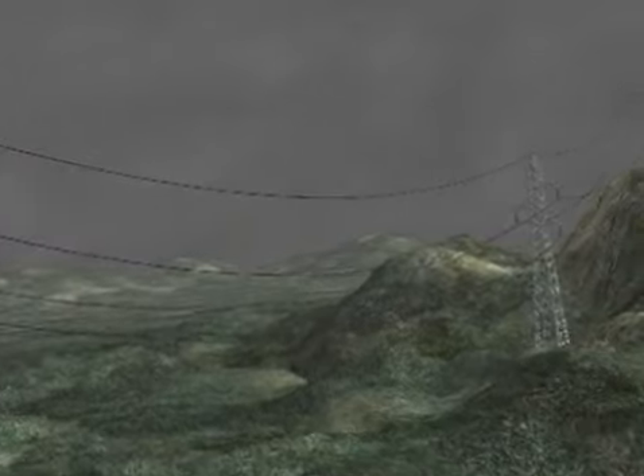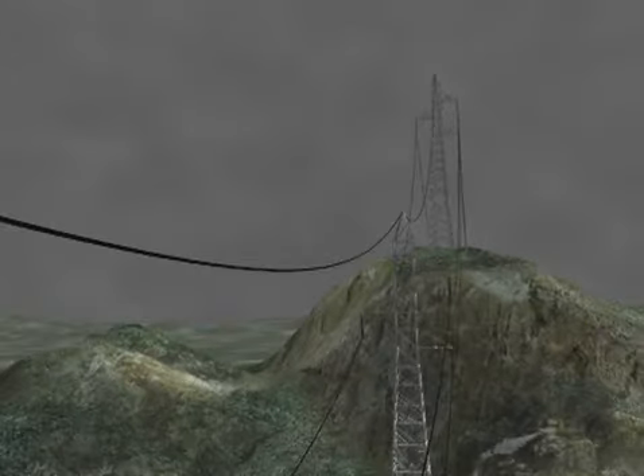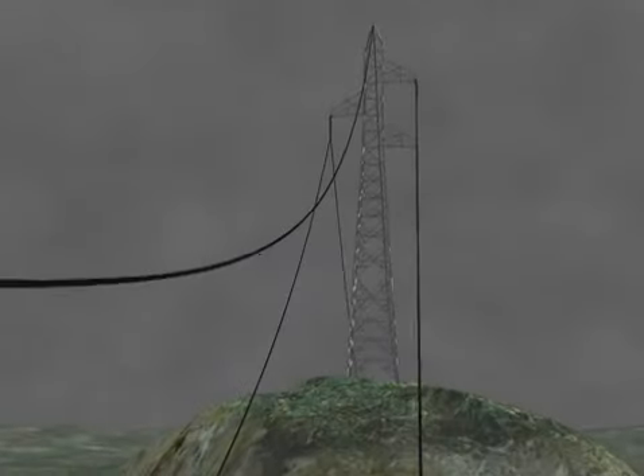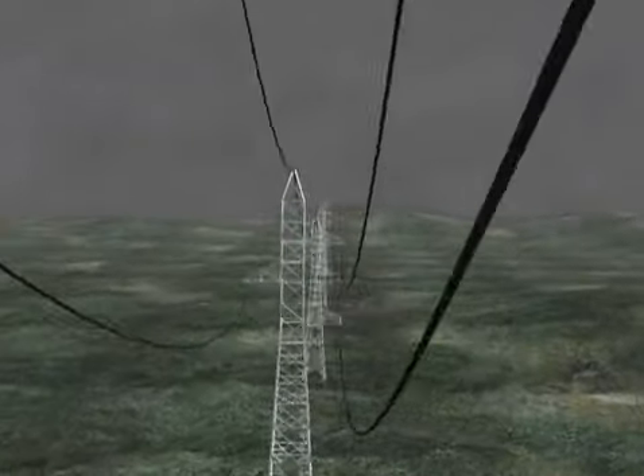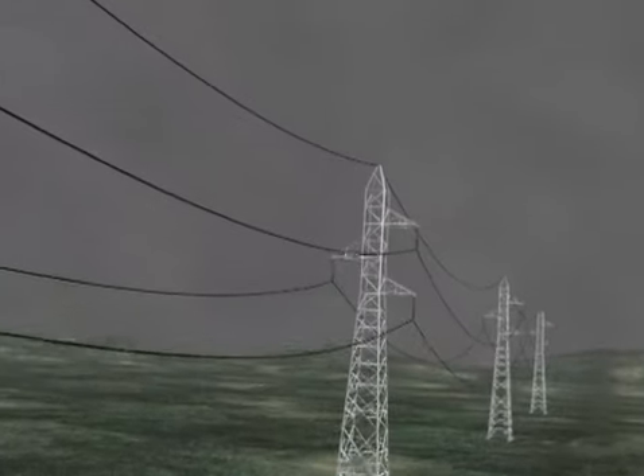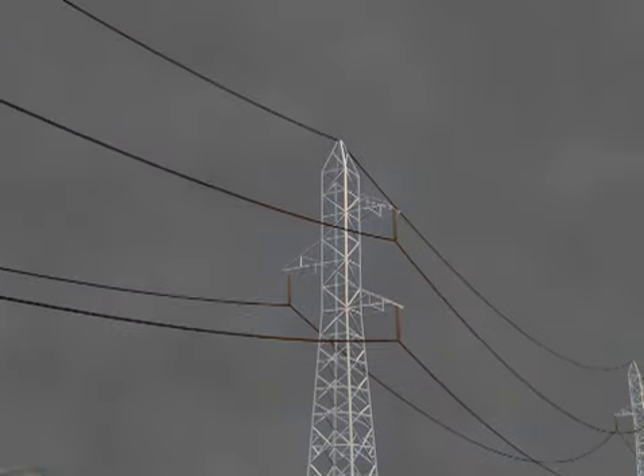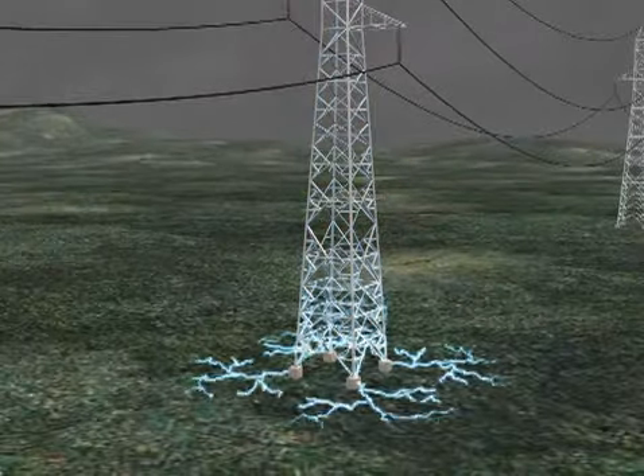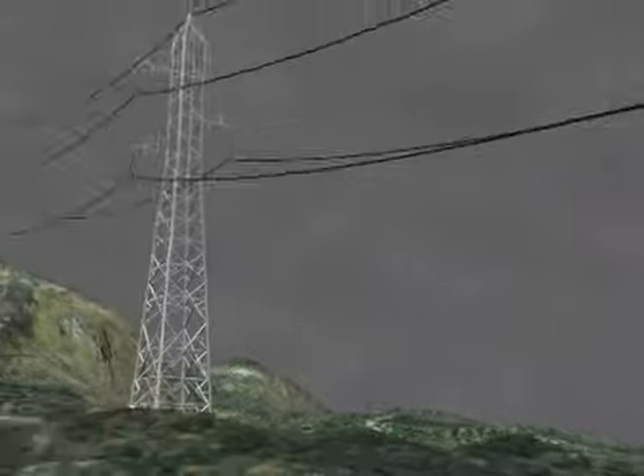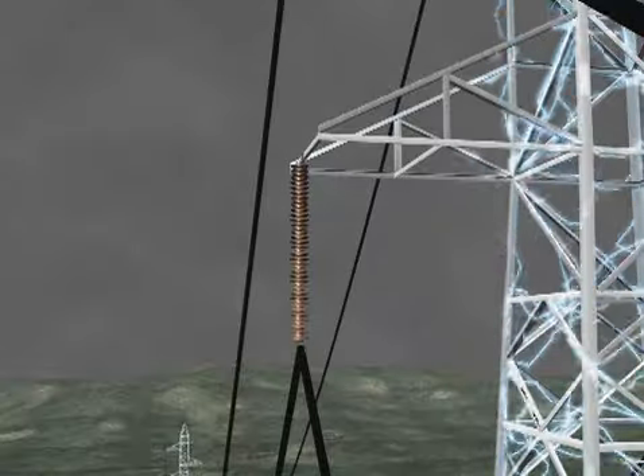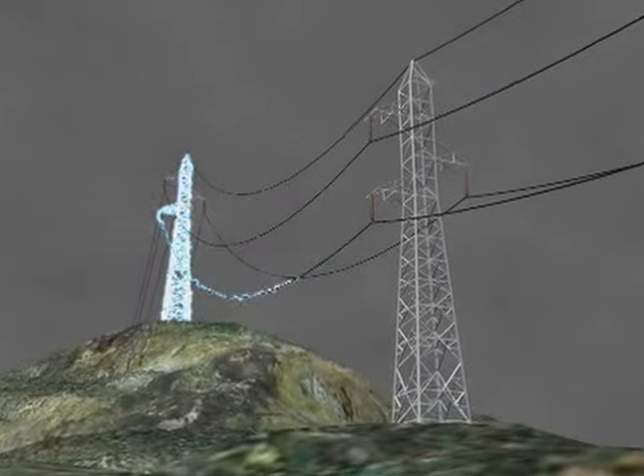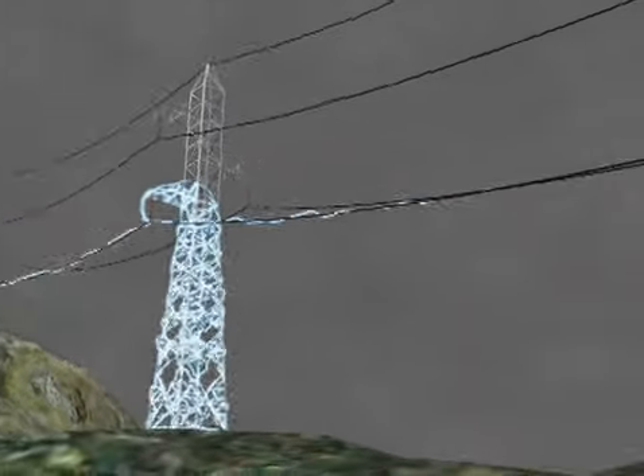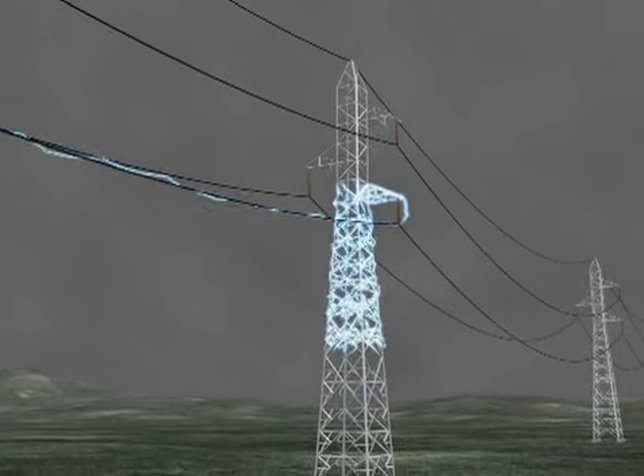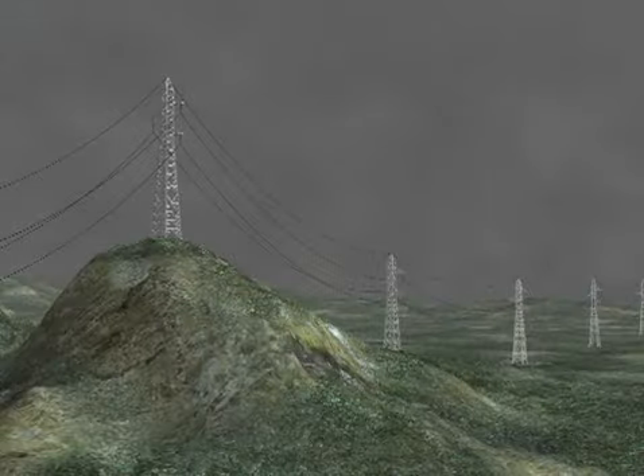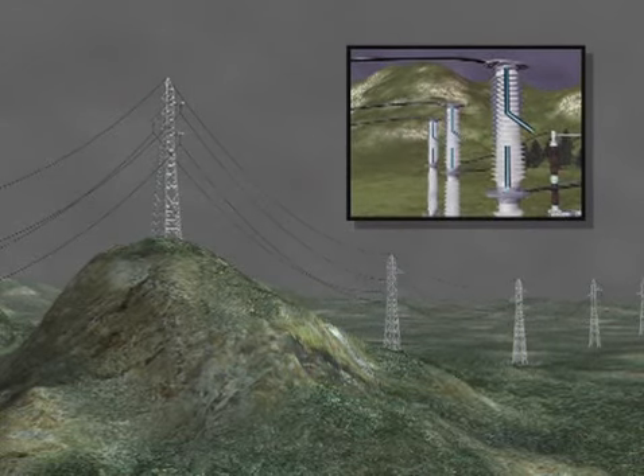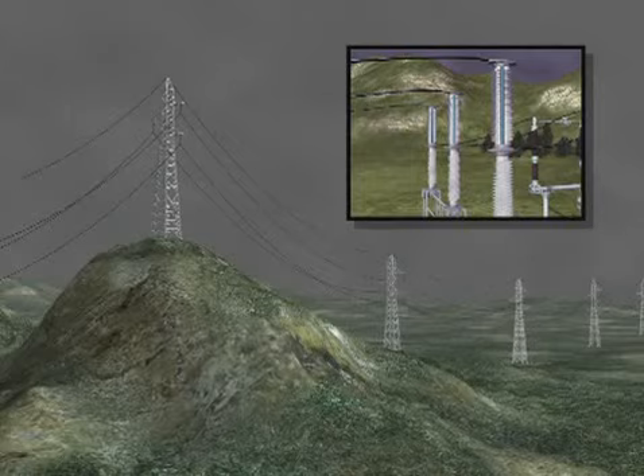Earthed overhead shield wires, optimally located in the towers along a power line, often provide good protection against lightning strikes across the line insulators. A basic condition, however, is that the towers are sufficiently earthed. When the power line passes through areas with high earth resistance, the protective capabilities of the overhead shield wires are reduced. In this situation, the risk of back flashovers across line insulators is significant. Any strike across a line insulator registers as an earth failure. The current is switched off at the station and then reconnected. A power outage has occurred.